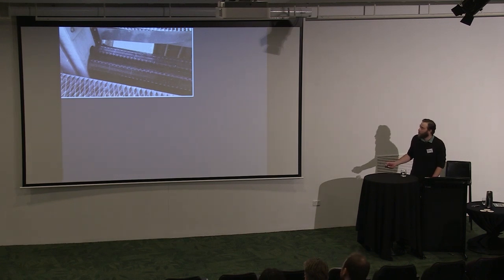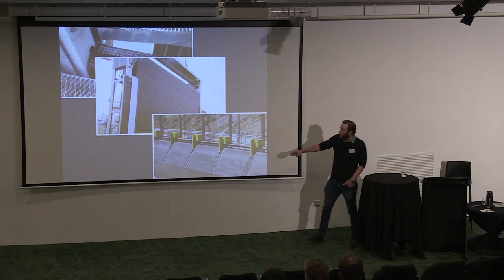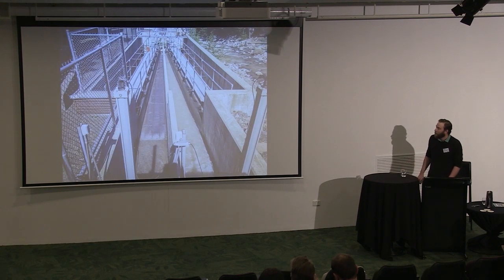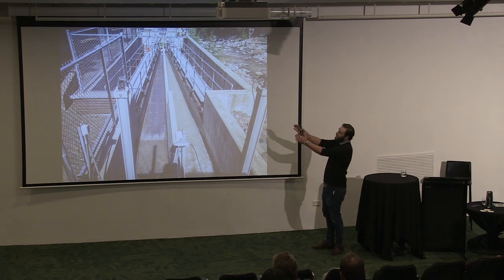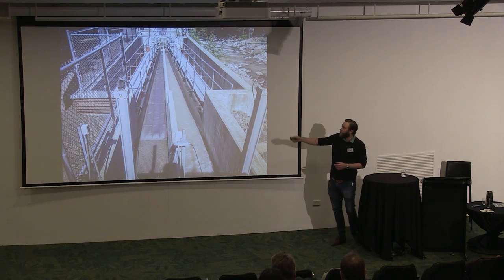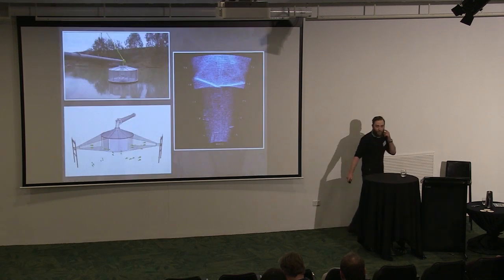This is another option called a traveling belt or escalator screen — lots of little panels just like an escalator in a shopping centre, rotating around. These are great for banks especially if you've got a lot of debris like algal mats or big logs, as that material can be lifted over. There are horizontal options too: water from upstream comes into flumes, and with a horizontal screen there's no suction so fish can swim quite freely and exit the system. You can scale it up to pretty massive installations.